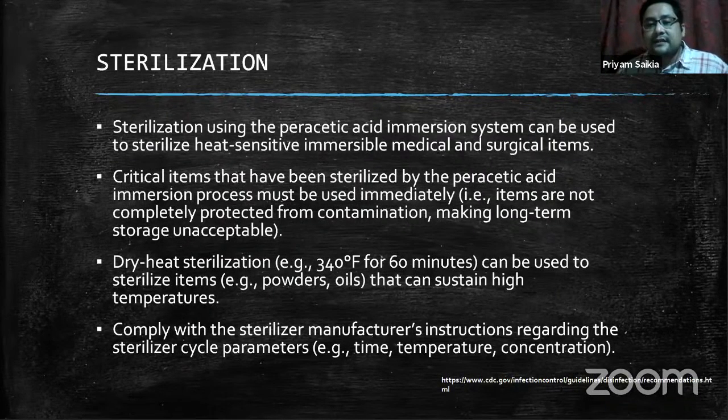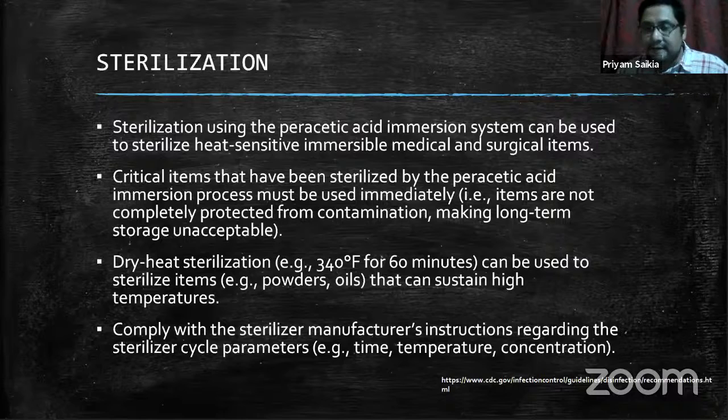Dry heat sterilization can only be used on substances that can withstand high temperature, like some powders, oils, or some natural suture materials. And CDC recommends complying with the sterilizer manufacturer's instructions regarding the sterilizer cycle parameters for any kind of sterilizing system that we are using.